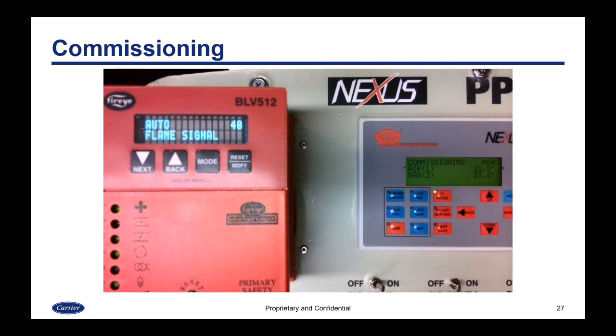Now I can do 0.4, etc. for as many points as you want to set for your curve. And then when you're done, you hit C mode so that it knows you've set enough points. If you want to add another, you hit next. Like I said, this was already commissioned, so I had points in it. So I was just walking through them, which is nice for when you lose your load during setup. All the points that you've saved, it'll go to that position the next time you start it up. You just have to confirm that they're where you want them to be.